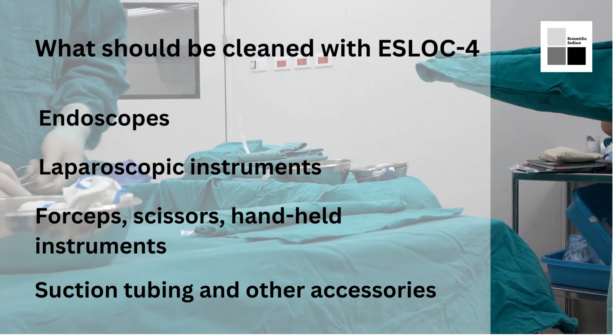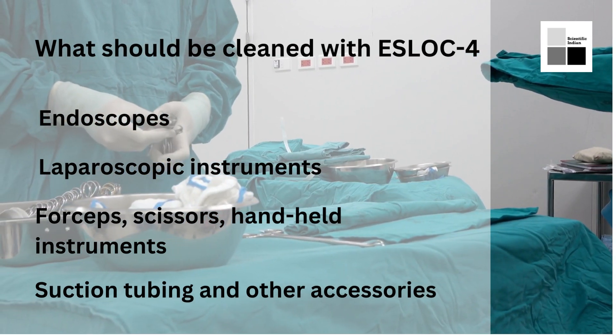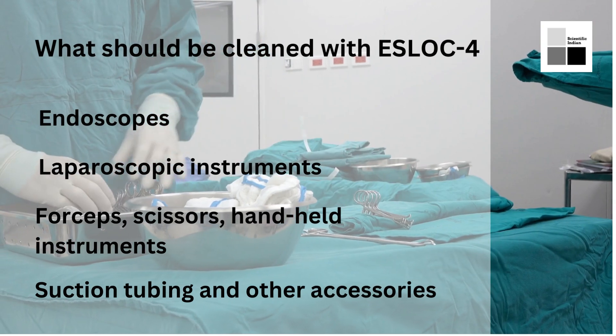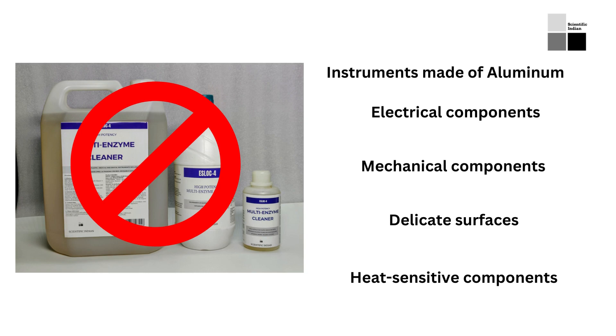It is important to note that ESLOC-4 multi-enzyme cleaner is not suitable for some types of instruments, such as those made of aluminum or other materials that can be corroded by the enzymes. Multi-enzyme cleaners can cause corrosion and damage to these types of materials, so it is important to use a cleaning solution that is appropriate for the material used in the instrument.